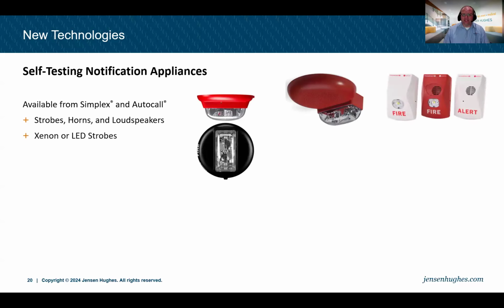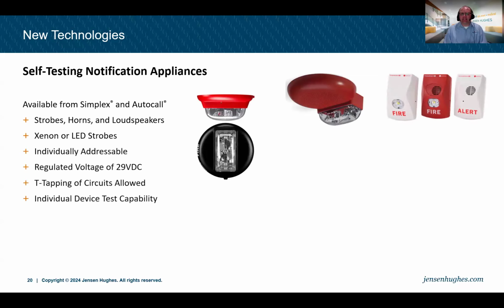And so whether you're using xenon strobes, kind of a little bit older technology, or newer LED strobes, it doesn't matter the technology there. Each device is individually addressable. And they actually use a regulated voltage of 29 volts. So as the voltage goes higher, the current goes lower. So we have quite a bit lower current draw. We have the ability to put more devices on a given circuit. And for the first time, you can T-tap a circuit if that's allowed in your jurisdiction, because all of the devices are supervised, are fully monitored for integrity.